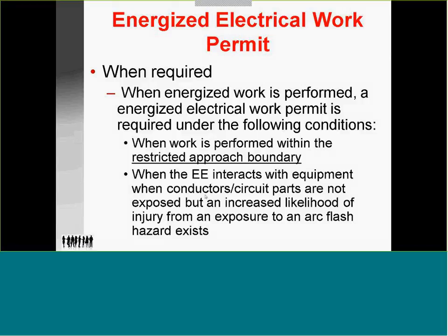Energized electrical work permit. When energized work is performed, an energized electrical work permit is required under the following conditions: when work is performed within the restricted approach boundary, that's the 12-inch boundary; when you interact with equipment where conductors or circuit parts are not exposed, but an increased likelihood of injury from an exposure to an arc flash exists. So if you've opened the panel and you're backed away from it, it's PPE if you're within the arc flash boundary.